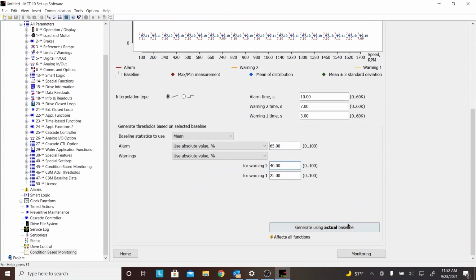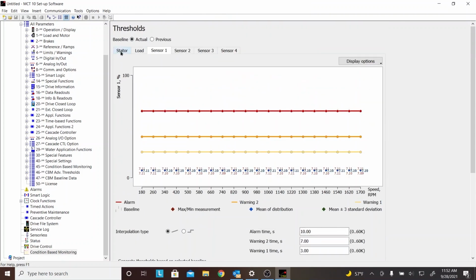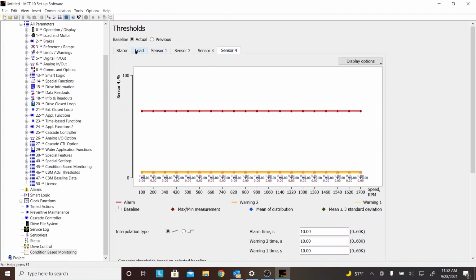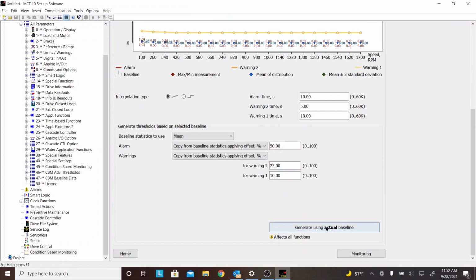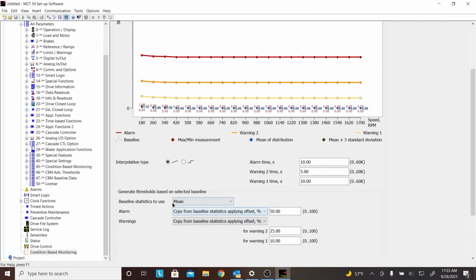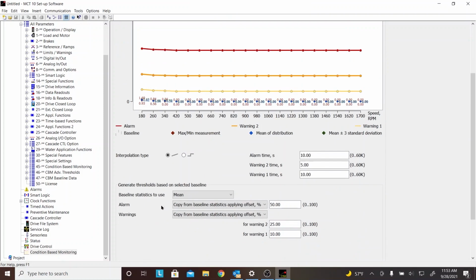So as we go down, we have a way to calculate, once we do all these settings in the different folders, and generate all those against the actual baseline. Now, remember, it affects all functions when you push this button. So what we want to make sure we do is set up all these folders first, whichever ones we're using. And then we will generate that. Now on the very bottom, we can go back to the home page at any time, or we can go straight to the monitoring page at any time. And once we're in the monitoring, that means it's live and it's monitoring the drives, it's running. Okay, so let's go back to home.